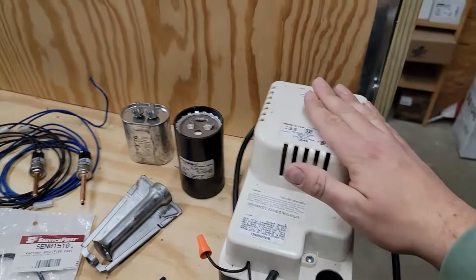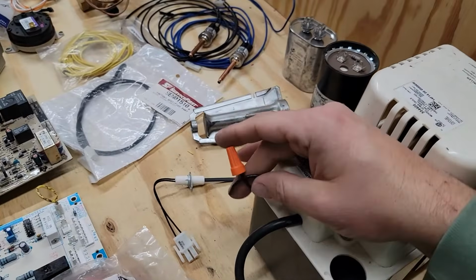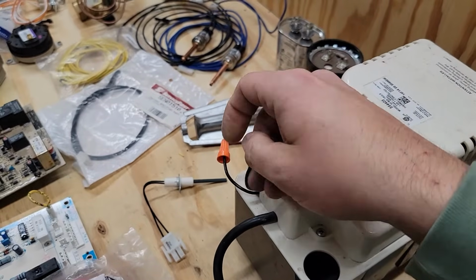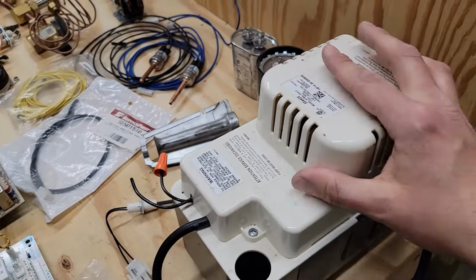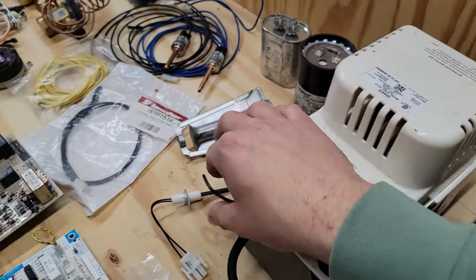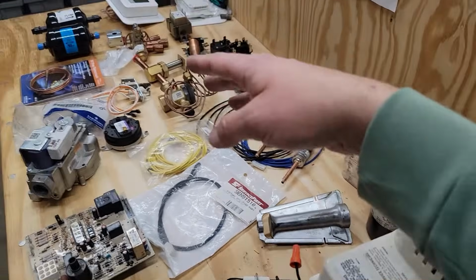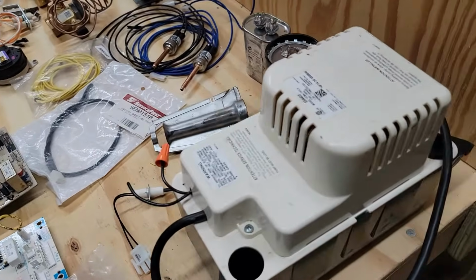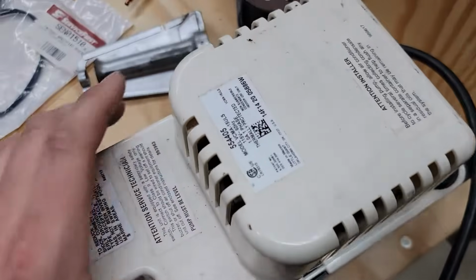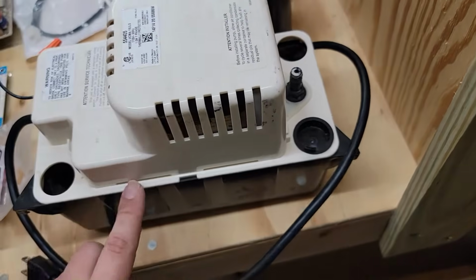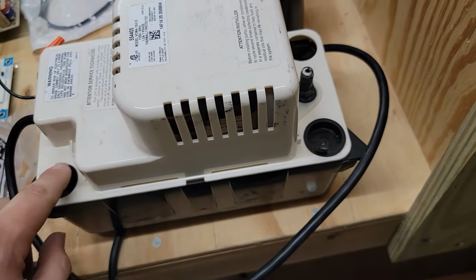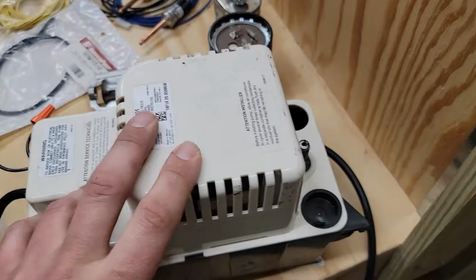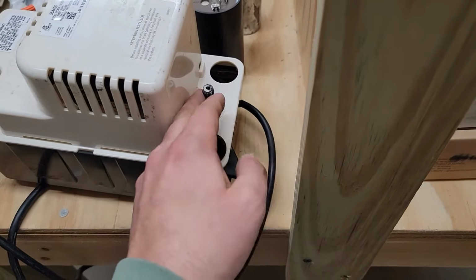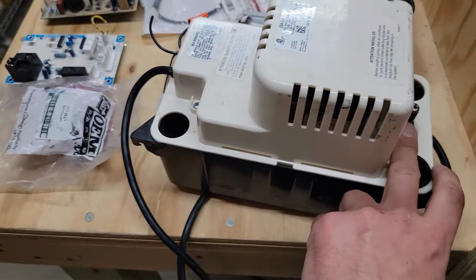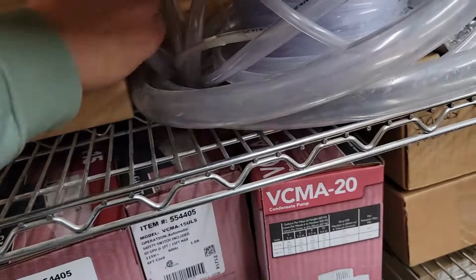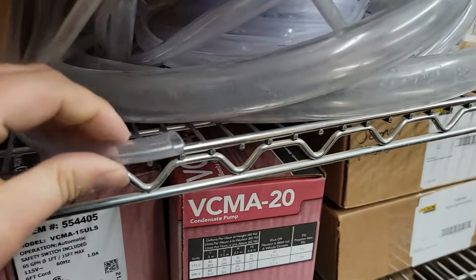Let's see, this is a condensate pump. Condensate pump has a normally closed, I'm pretty sure, switch. And whenever it gets too high, then that will open a circuit, and you can tie this in with your thermostat so that it shuts the power down, and that way you don't have any water in your floor. Condensate pump has a motor, and whenever the float engages inside this reservoir, that's when it will energize the pump, and then it'll send water through this little barb fitting here, and this fits a 3/8 tube. So if you want to know what a 3/8 tube looks like, this is some 3/8 tubing right here.